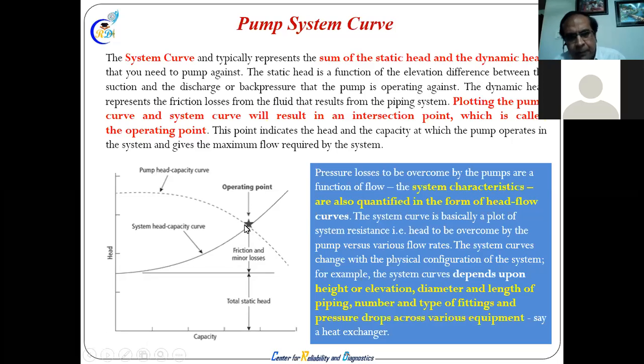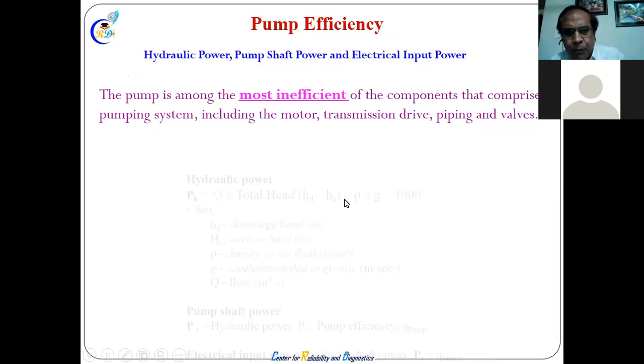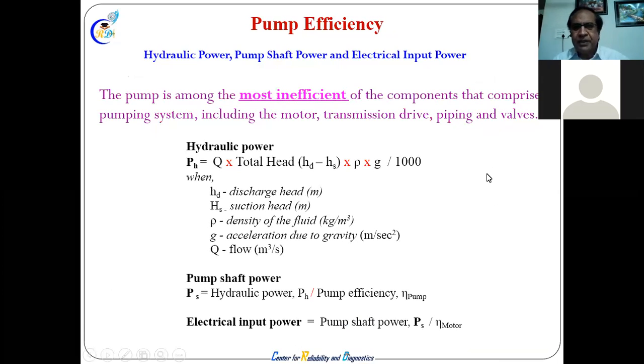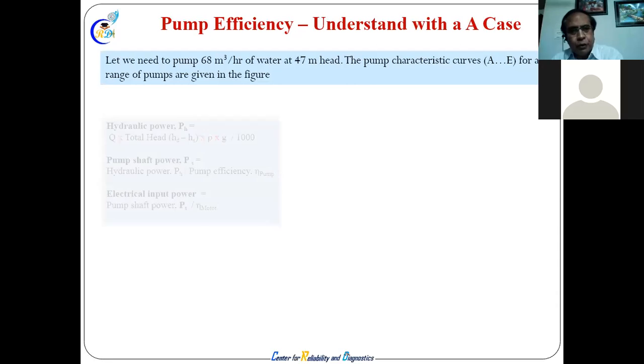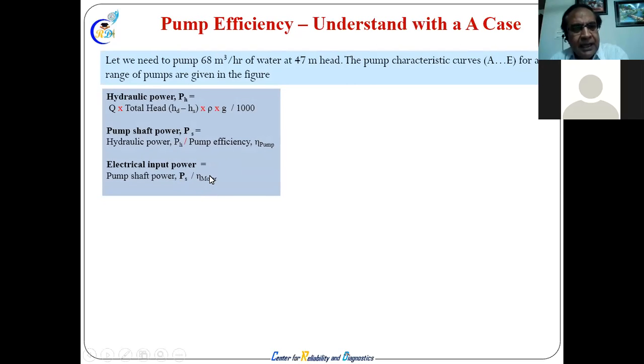And this point is the operating point, the best efficiency point. In this pumping system, the most inefficient part is the pump itself, because it is a mechanical part. If the hydraulic, static head and other things are taken care of properly, the least efficient is the pump itself. That's why hydraulic power is always lower than shaft power. If you take that into account, the electrical input will be much higher than the shaft power, and shaft power will be much higher than the hydraulic power.